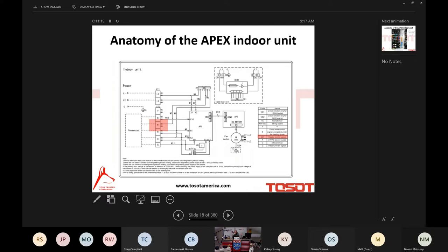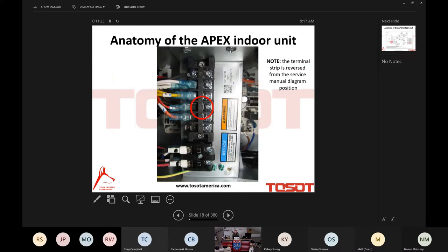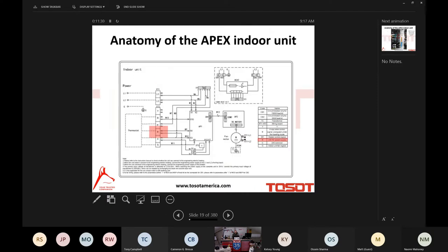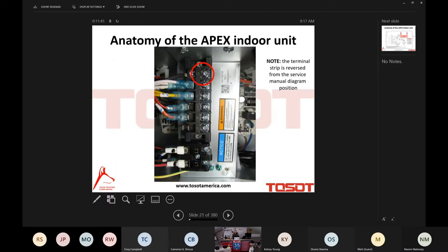And we'll talk about that. In fact, I'll show you that in some great detail as we move forward. And that is the signal for the electric strip at W1 to power up. The R terminal is our 24-volt power circuit. Our C terminal is our 24-volt common. And lastly, our G is our indoor unit fan signal to operate.